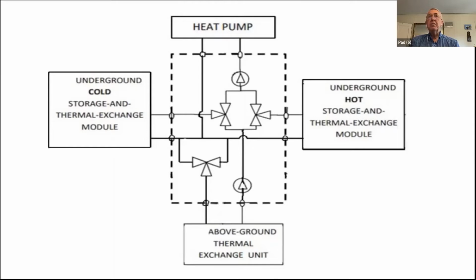So now we have 2 underground regions. We've got something called an above ground thermal exchange unit, and we gave it that name because it could be a solar thermal collector, it could be an air to liquid heat exchanger, or a combination of those things. But in general, it's meant to be something above ground that has either warm or cold water that can be fed into the system.